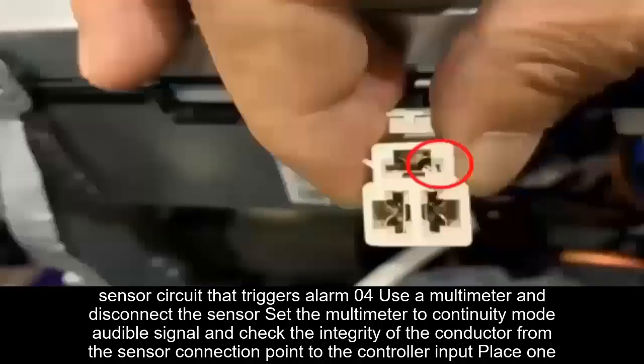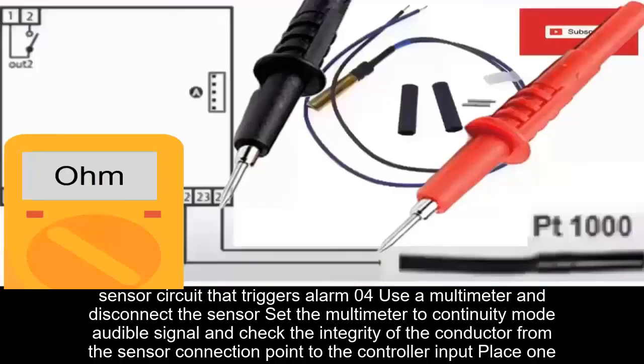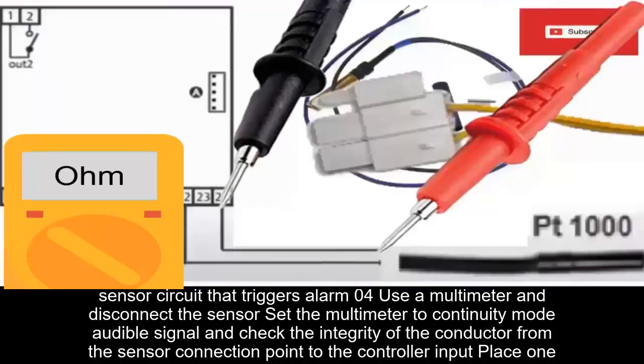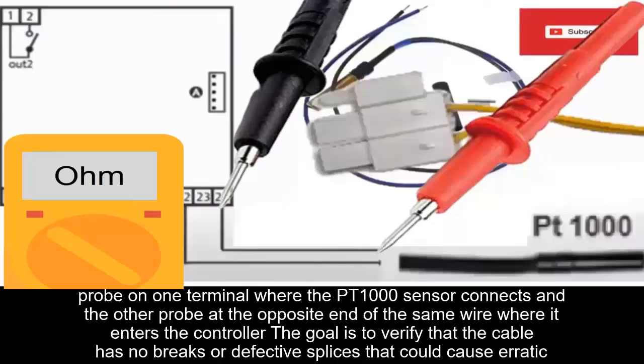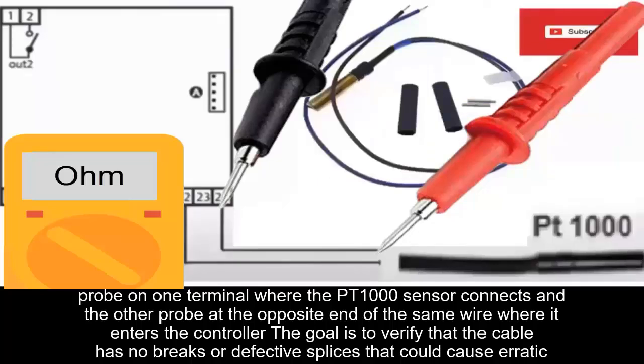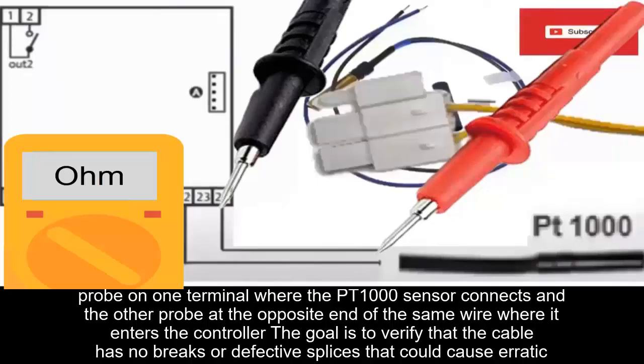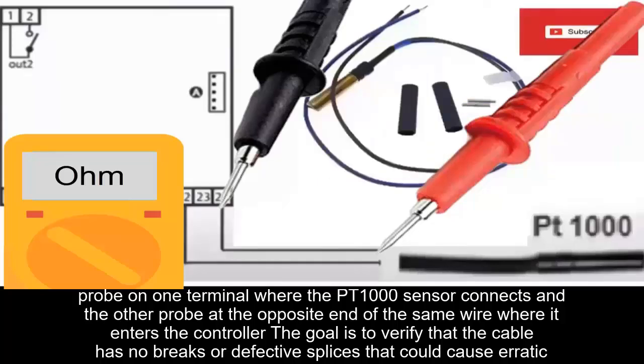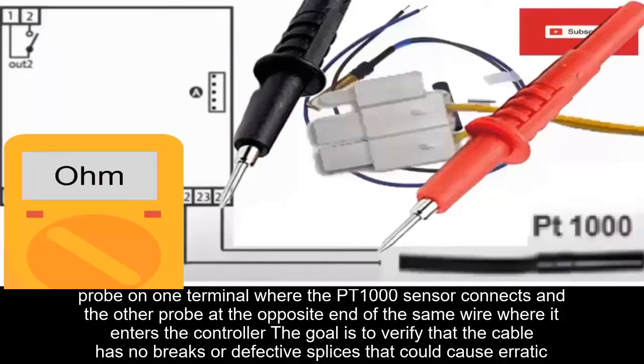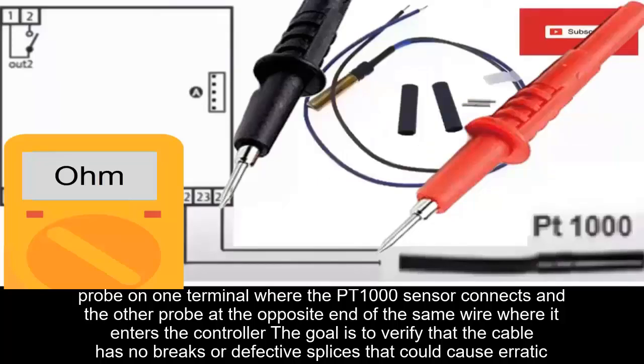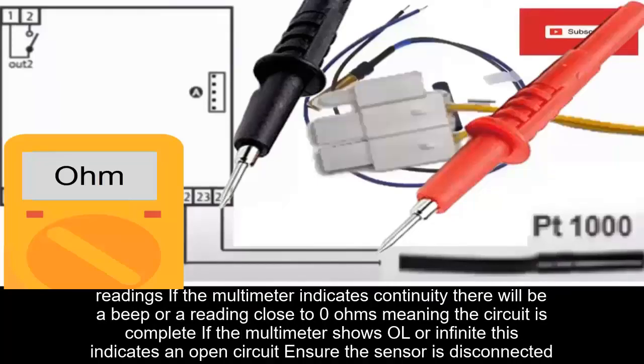How to measure continuity of the circuit that triggers alarm 04. Use a multimeter and disconnect the sensor. Set the multimeter to continuity mode, audible signal, and check the integrity of the conductor from the sensor connection point to the controller input. Place one probe on one terminal where the PT1000 sensor connects and the other end of the same wire where it enters the controller. The goal is to verify that the cable has no breaks or defective splices that could cause erratic readings.